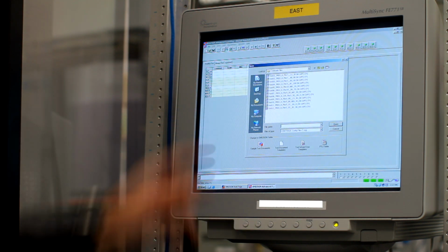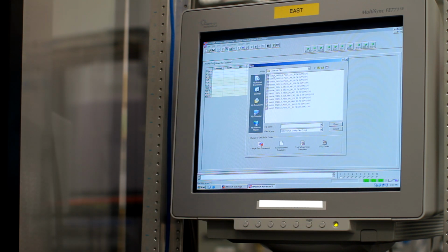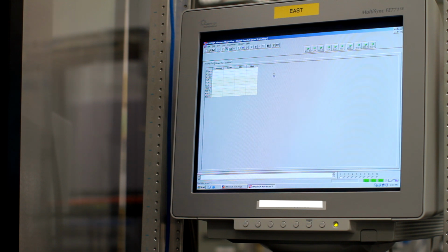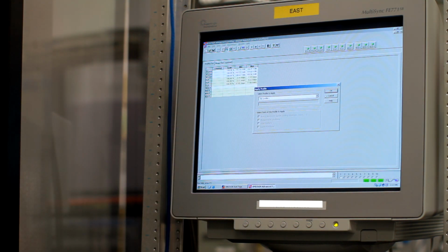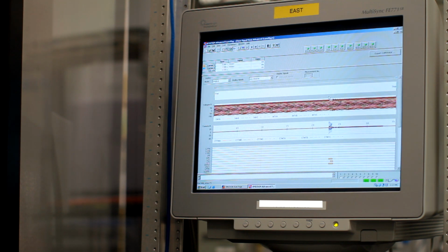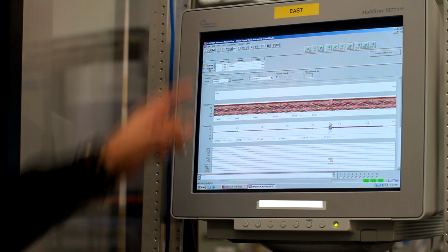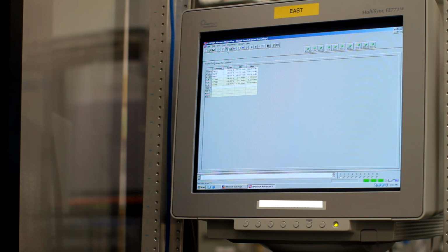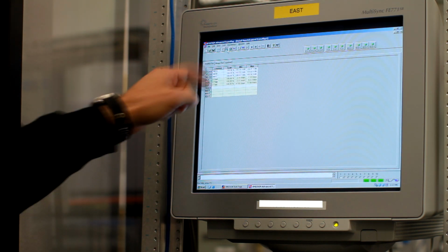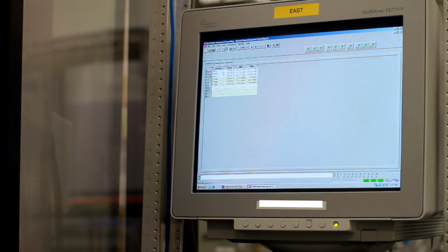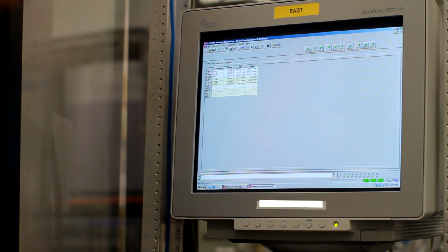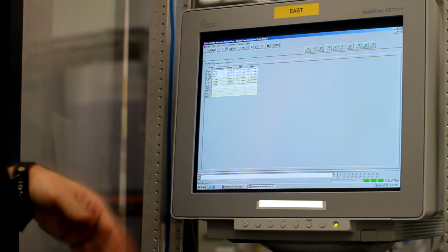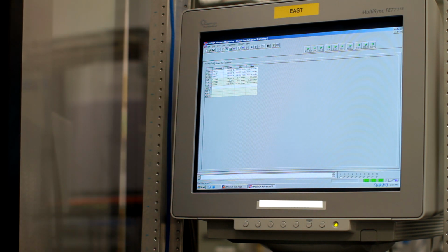Here's the list of COMTRADE files. We're going to select Test 1 here at the top. Double click on it, and when this Apply Profile box comes up, you just hit Cancel, and now you go to Detail View and you start assigning the terminals according to the COMTRADE file you want to apply. In this case, the Omicron will apply the topmost set of traces to this default window, and you have to make sure it's the right terminal.